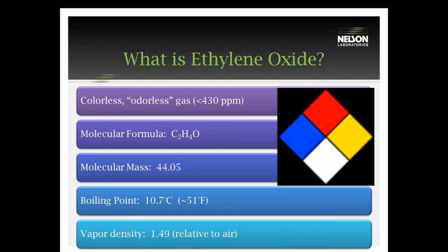Ethylene oxide sterilization is a commonly used low-temperature sterilization process. It uses ethylene oxide gas, which is a colorless, odorless gas. It is a known carcinogen and mutagen, so you take extra precautions when using this sterilization. These are just some scientific facts about the molecule and give you a brief, quick overview of the molecule itself.